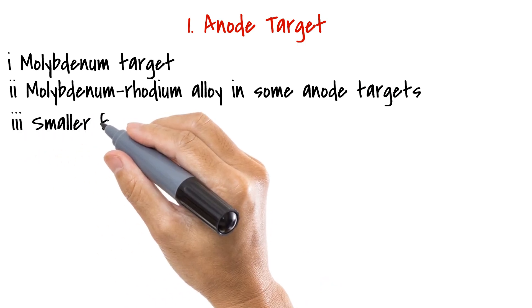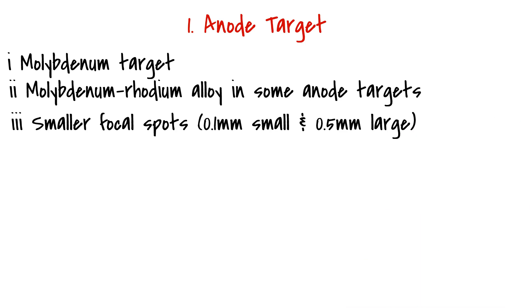Lastly, mammography anode targets also differ from conventional targets in their focal spots. Mammography tubes have a significantly smaller focal spot for increased resolution — 0.5mm focal spots for regular use, and an even smaller 0.1mm focal spot for magnification images.